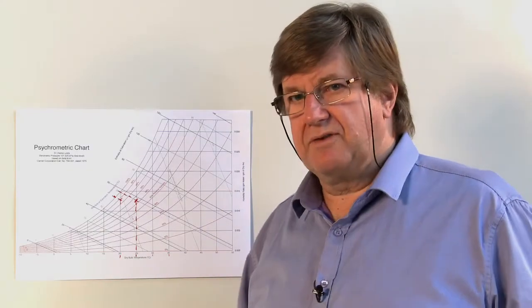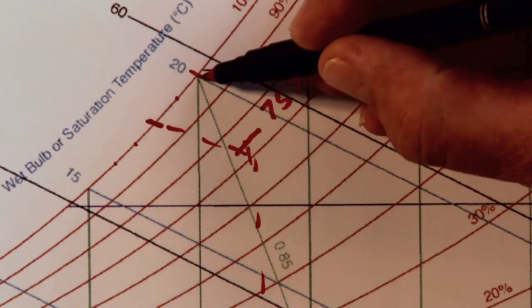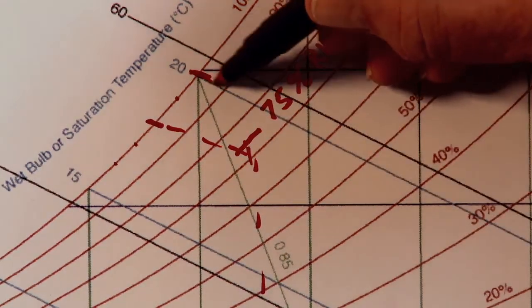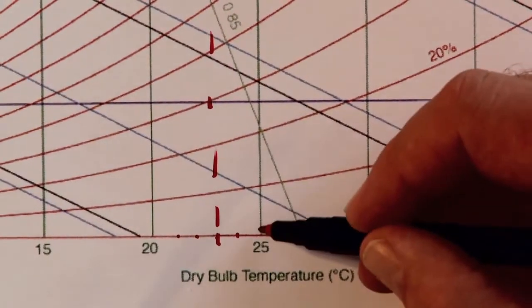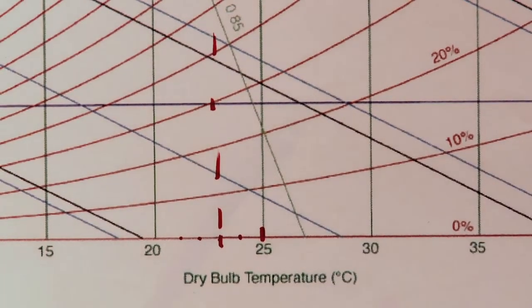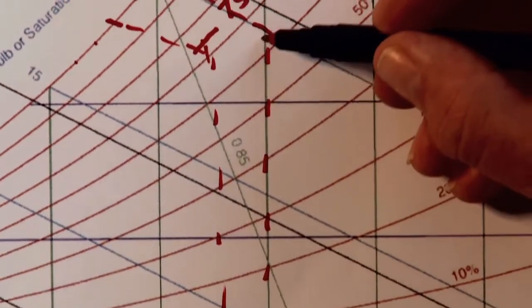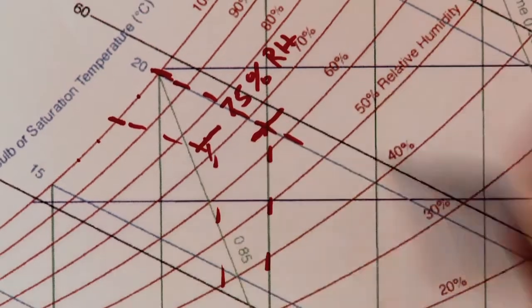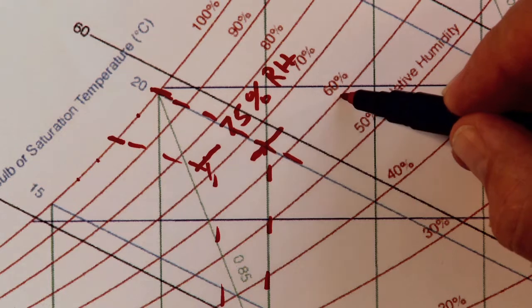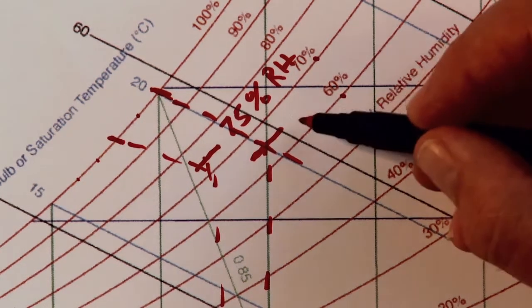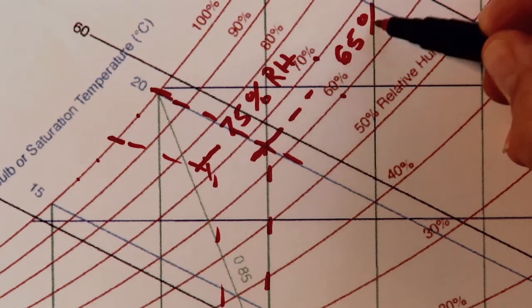Let's do one more example. Say we've got a wet bulb temperature of 20 degrees Celsius and a dry bulb temperature of 25 degrees. We plot up this graph and the intersection of these two points tells us the relative humidity — between 60% and 70%, so we would have a reading of 65% relative humidity.